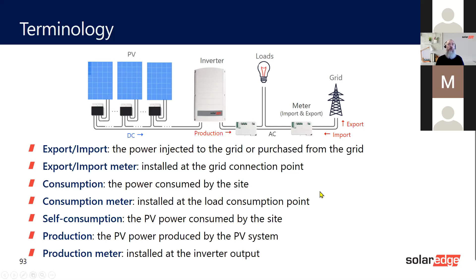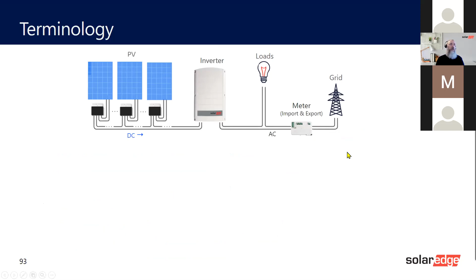Very good information that the inverter needs, because then it will tell the battery whether to charge or discharge. In the other terminal you can list the consumption meter, self-consumption, and production meters as well, depending where you put it. But we mainly want it on the import and export here.